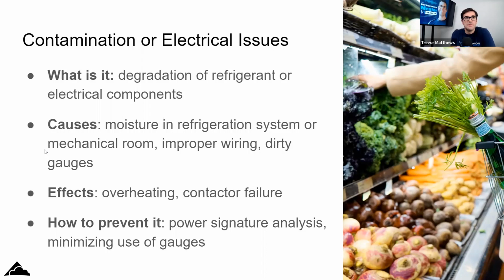So a lot of what happens out there, what I see more and more, is that contractors will replace a compressor, even if it's a valve plate, just in case there's something else going on and the technician misses that. So they'd rather, for their customer, replace an expensive compressor instead of just doing a little bit of repair, because say that compressor is 8 years old already, and then they do a really expensive repair and it only lasts another 6 months or a year, then it would have been better for them to replace that compressor. So there is a fine line as well. Yeah. And Joe would know this. Sometimes you have to make a decision. Let's do a repair. Let's do a replacement. And that's up to the call of the technician. Yep. Makes a lot of sense.